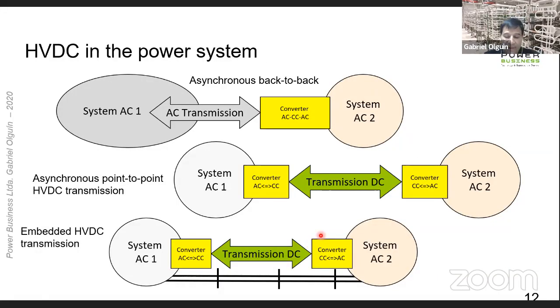So how can HVDC be used in a power system? Depending on the application, HVDC plays different roles. The most common HVDC applications are point-to-point transmission, back-to-back interconnectors, and more recently, embedded HVDC systems. In a point-to-point HVDC application, a long transmission line, either overhead, subsea, or underground, connects two converter stations to move massive electric power between the two isolated systems.